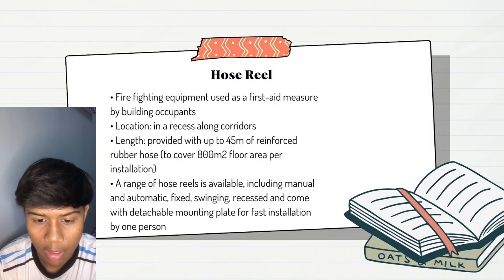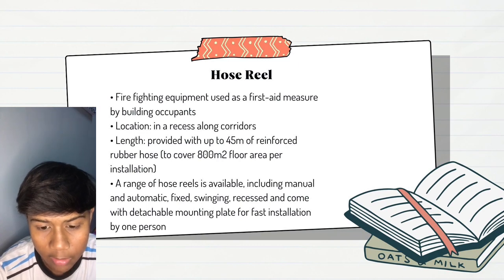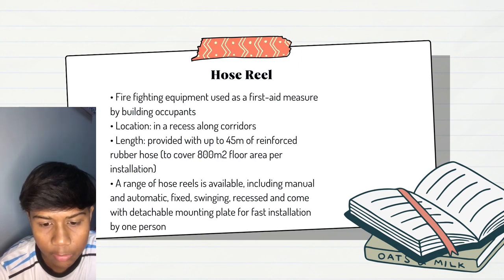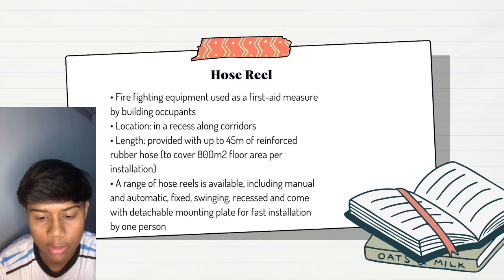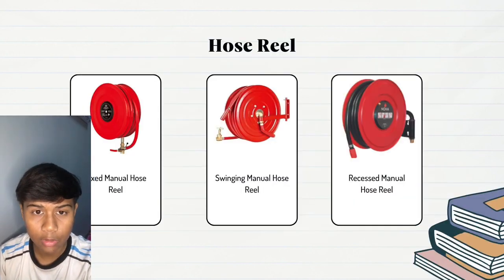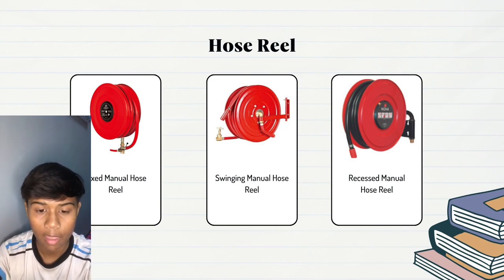Okay, next. Hose reel. Firefighting equipment used as a first aid measure by building occupants. Location, in a recess along corridors. Length provided with up to 45 meters of reinforced rubber hose to cover 800 square meters of floor area per installation. A range of hose reels is available, including manual and automatic, fixed, swinging, recessed, and they come with a detachable mounting plate for fast installation by one person. Lastly, I want to tell about hose reels. There are three types of hose reel. First, the fixed manual hose reel. Second, the swinging manual hose reel, and the last one is the recessed manual hose reel. Okay, that's all from me.